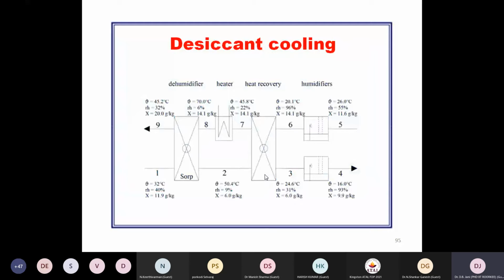Some data regarding actual measurements of temperature as well as humidity: suppose we take the ambient temperature for a typical measurement as 32 degrees. After desorption it may rise to 50 degrees. Heat recovery will bring it to 24, and ultimately the cooler can maintain it at 16 degrees. Similarly, if the RH is available at 40%, it can be lowered to 9%, then increased to 31%, and with the help of the evaporative cooler it is maintained to keep the humidity ratio as per the comfort point temperature on the psychrometric chart.